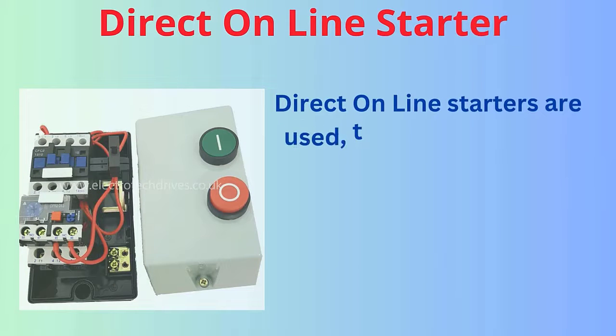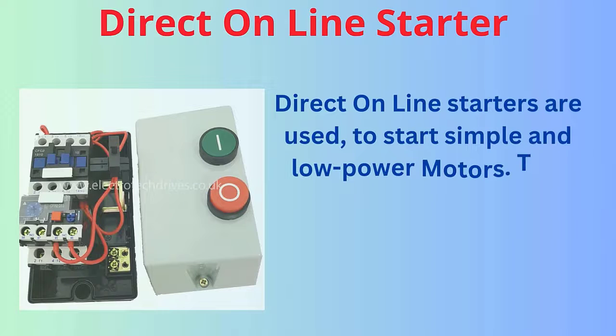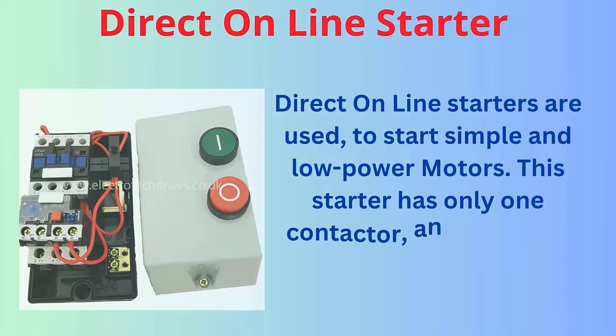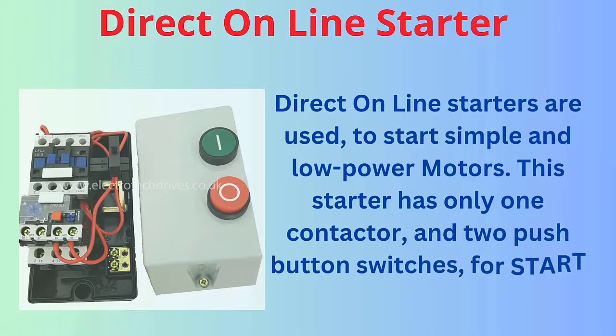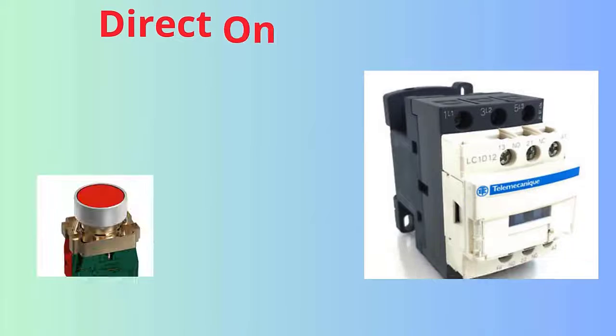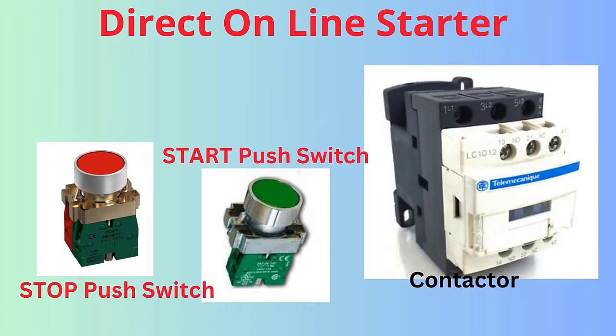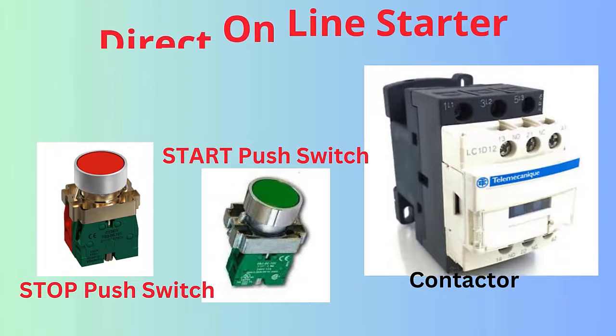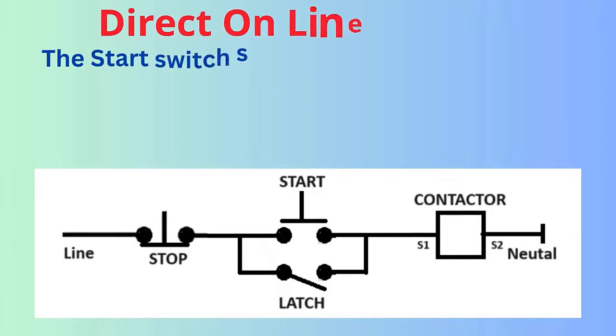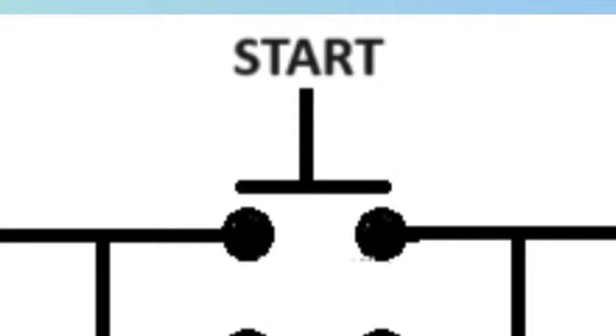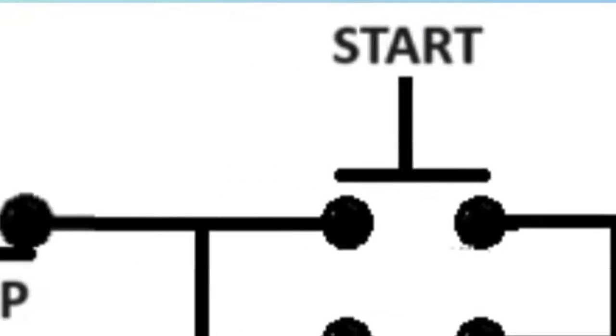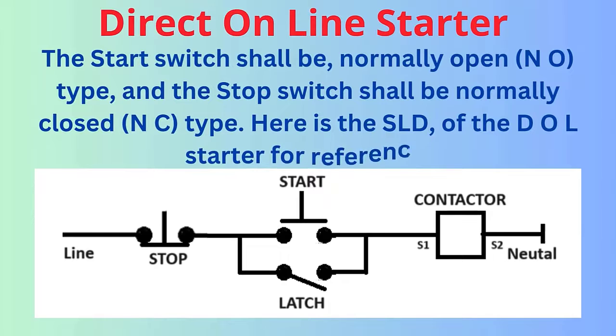Direct on-line starters are used to start simple and low power motors. This starter has only one contactor and two push button switches for start and stop. The start switch shall be normally open type, and the stop switch shall be normally closed type. Here is the SLD of the DOL starter for reference. Let us see how the starter is working.